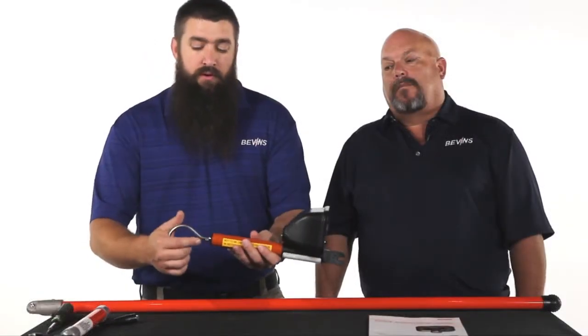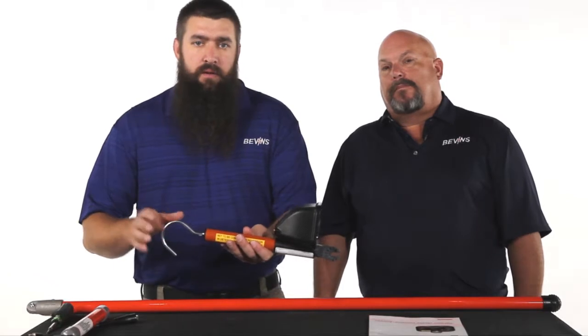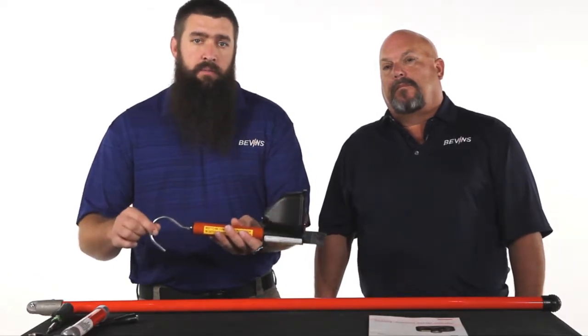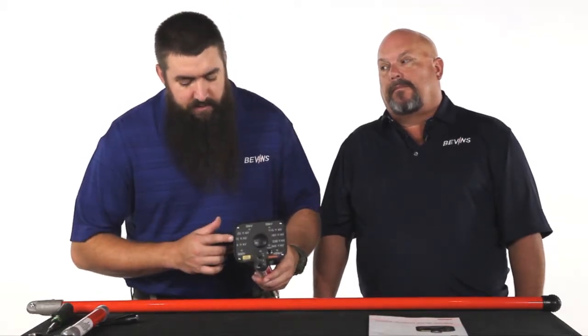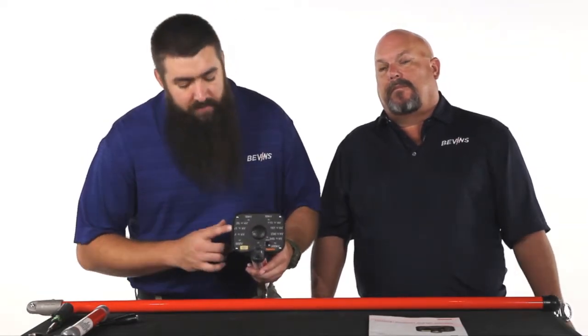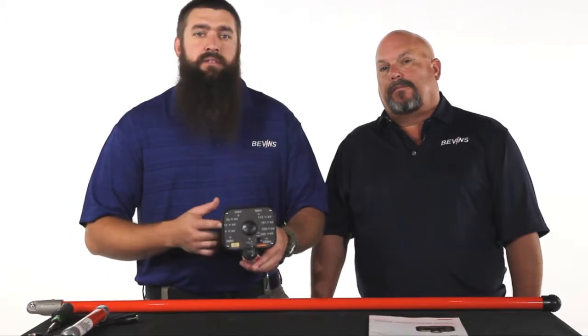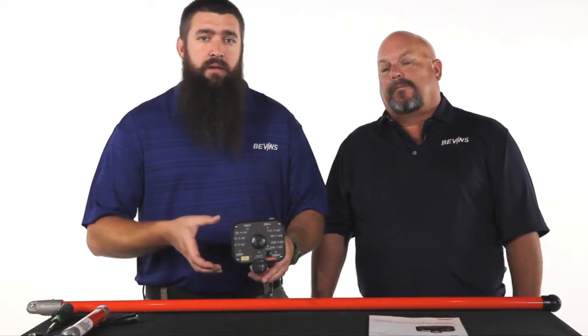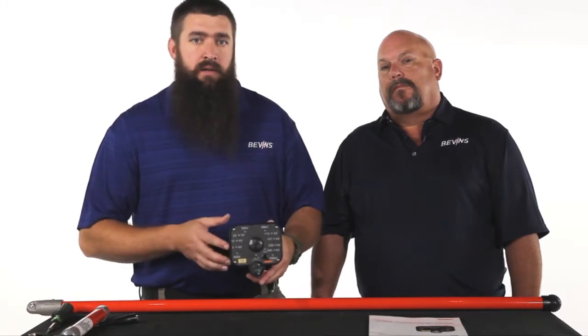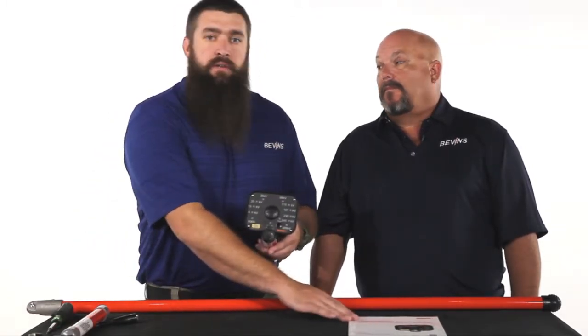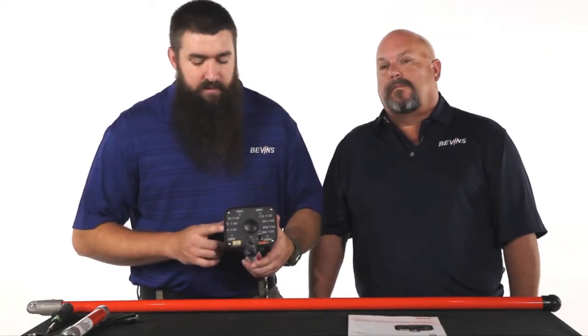The way the unit works is it is a contact type device, so the live conductor does need to make contact with the input probe here in order to register voltage on the display. But let's say that you had, for example, the 15 kV LED blinking and the audible alarm chirping at you. What that basically means is you're someplace in between 6.6 kV and 17 kV, so there's a window that can be present to illuminate that LED and so forth for the rest of the LEDs. There's a chart that outlines this clearly in the instruction manual that comes with each tool, so you'll be able to translate the readings quite simply.